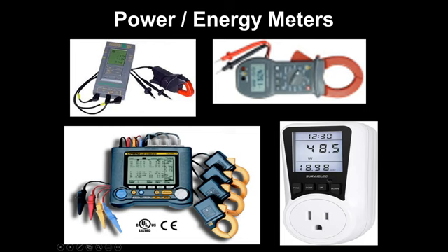This is the cheaper one. This comes as a single unit, like a tong tester with a voltage probe. You just clamp it for one phase, and connect the other to get the voltage reading. This is the cheaper one. This is more expensive, and this is the most expensive. Of course, here again you get different types depending on the sampling rate and other parameters. This is a plug-in meter. I think this is simple. You have probably taken it from Amazon, and many of these meters are Chinese, so you have to have an adapter here. You cannot directly connect it.